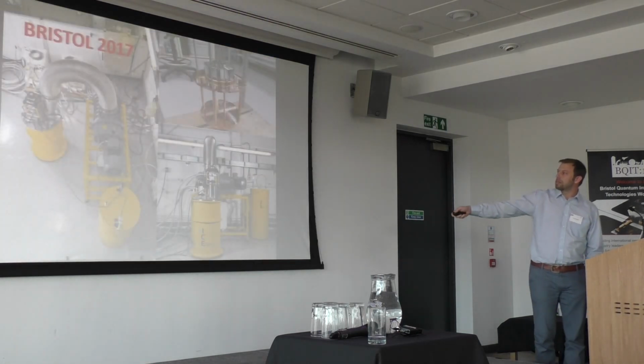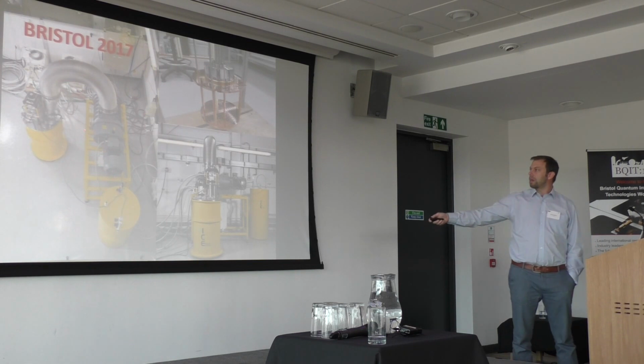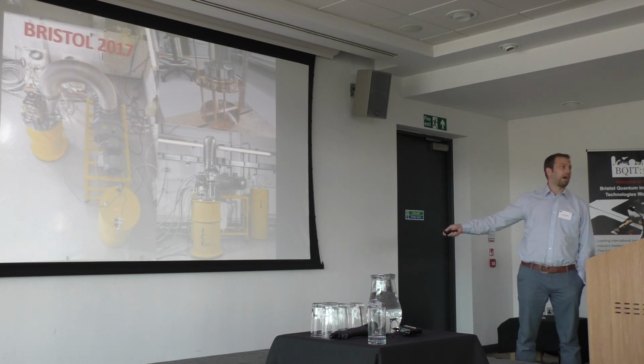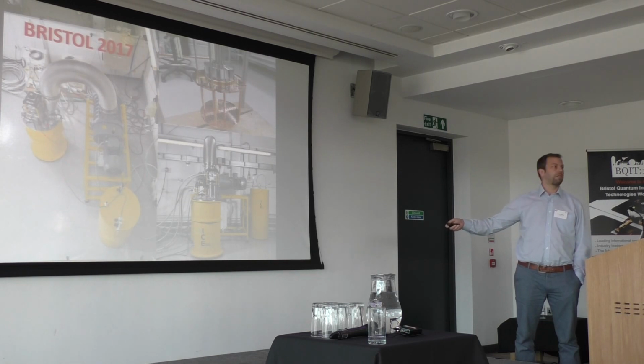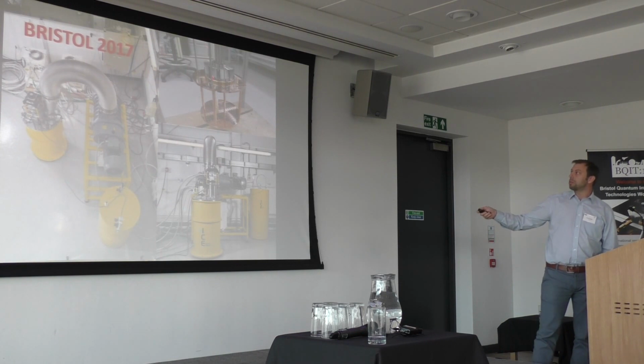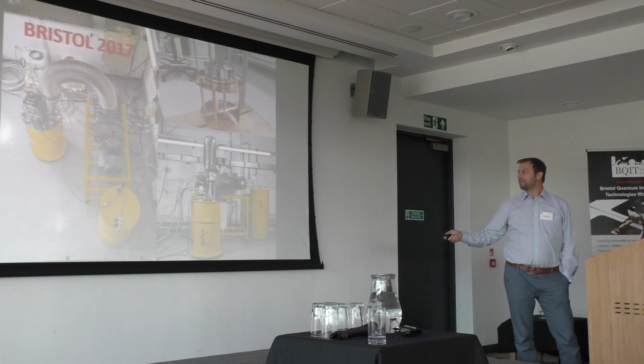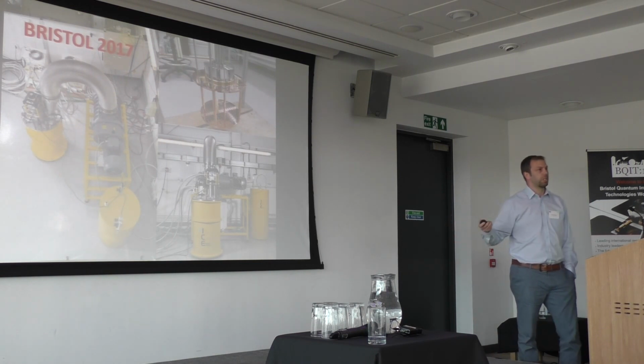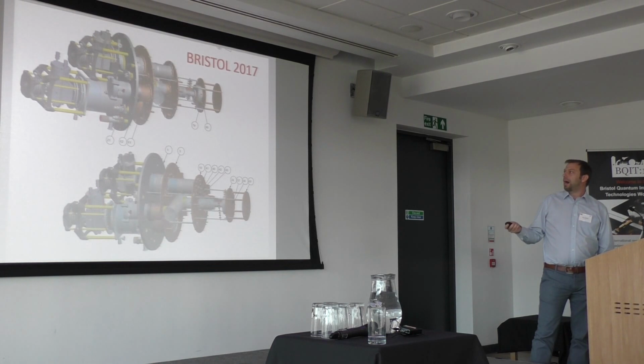Going back to this one — what we're having to do is store high purity helium gas and feed it into the system. We then liquefy that room temperature gas as quickly as we can to feed it into the 1K pot, because at the same time we're feeding it in, we're pumping it out with this huge pump, as fast as it can. It then feeds out of the back of the pump, back into here, and the whole thing runs continuously on a loop.